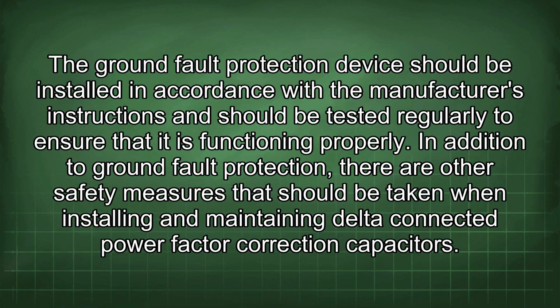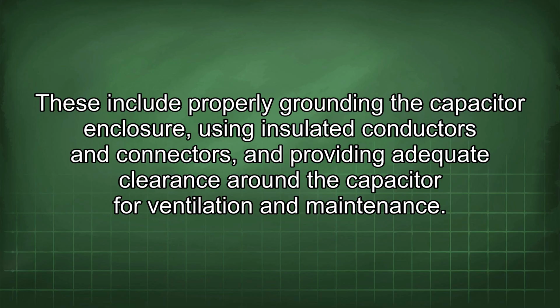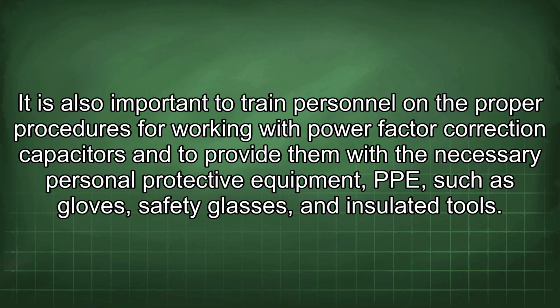In addition to ground fault protection, there are other safety measures that should be taken when installing and maintaining delta-connected power factor correction capacitors. These include properly grounding the capacitor enclosure, using insulated conductors and connectors, and providing adequate clearance around the capacitor for ventilation and maintenance. It is also important to train personnel on the proper procedures for working with power factor correction capacitors and to provide them with the necessary personal protective equipment (PPE) such as gloves, safety glasses, and insulated tools.